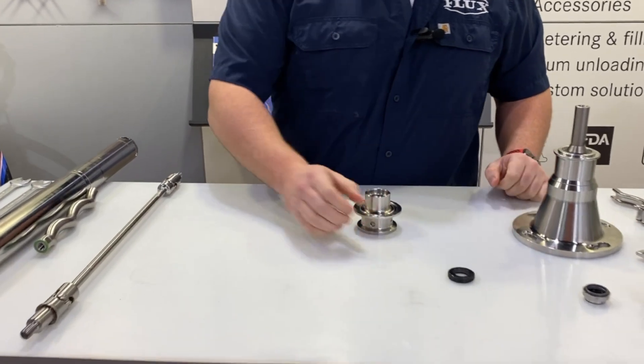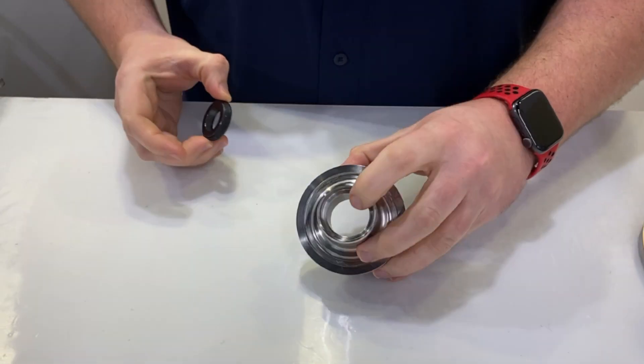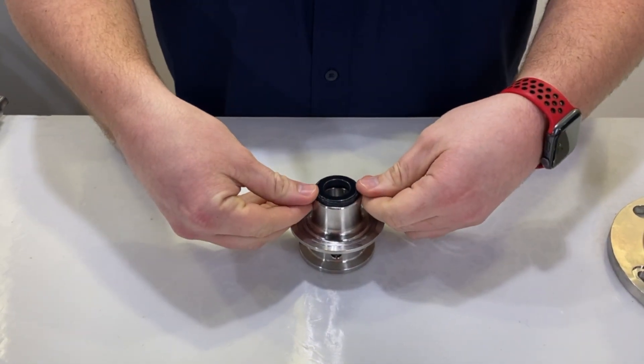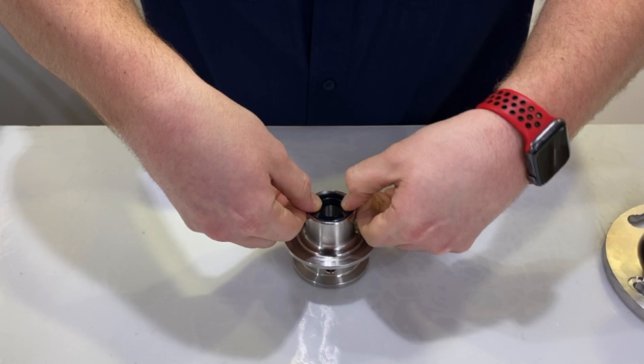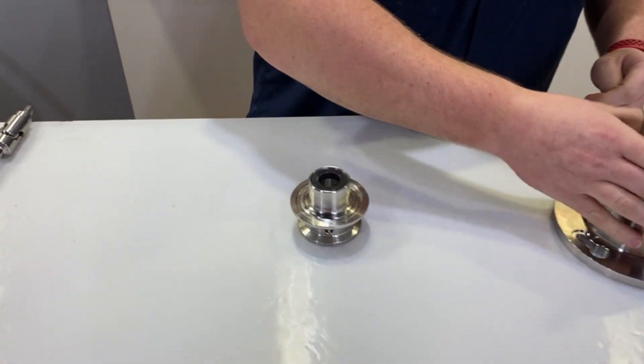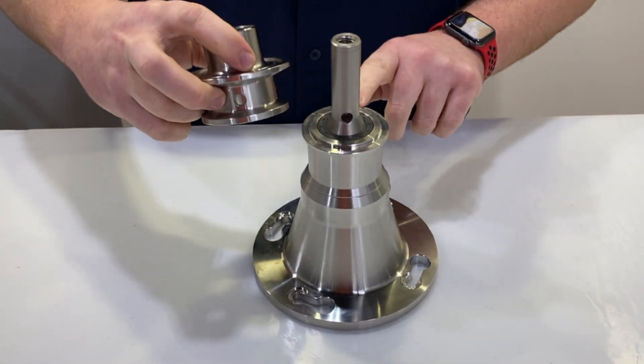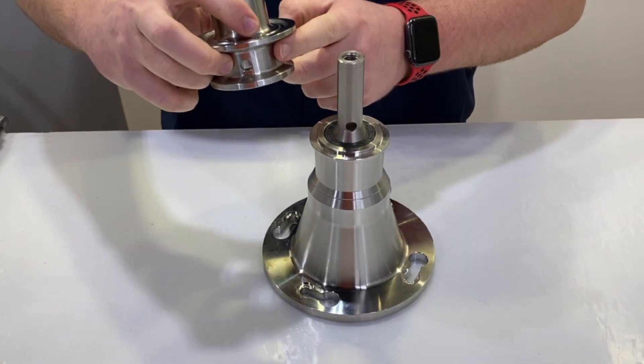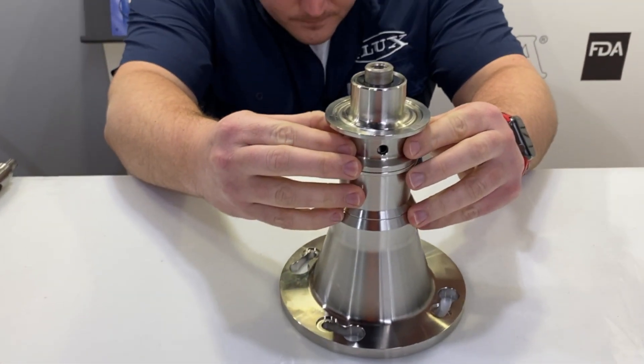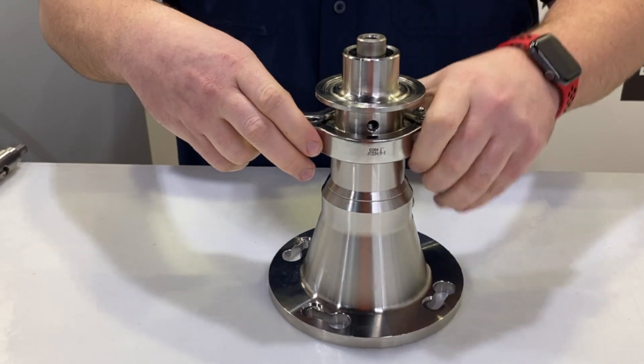We'll then reinstall our seal, starting with the stationary face. It sits down on this shoulder here in the motor connection piece. Press the stationary face firmly down. When doing so, just be sure that your hands are clean as you don't want to get any particulates on the seal face which would cause damage. Then we will install the motor connection piece back onto the bearing flange, aligning the two sight windows, and secure that in place with the smaller of the two tri-clamps.